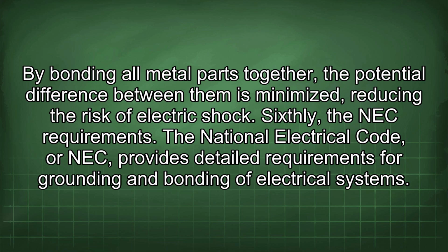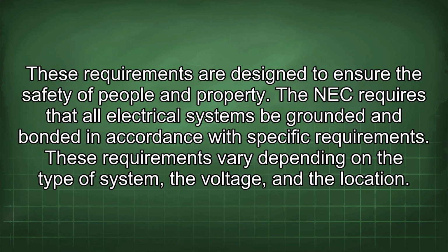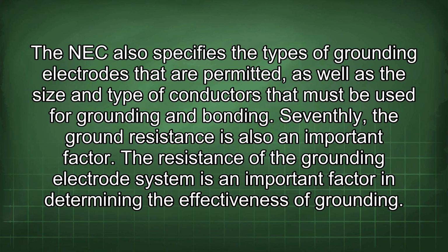Sixthly, the NEC requirements. The National Electrical Code, or NEC, provides detailed requirements for grounding and bonding of electrical systems. These requirements are designed to ensure the safety of people and property. The NEC requires that all electrical systems be grounded and bonded in accordance with specific requirements. These requirements vary depending on the type of system, the voltage, and the location. The NEC also specifies the types of grounding electrodes that are permitted, as well as the size and type of conductors that must be used for grounding and bonding.